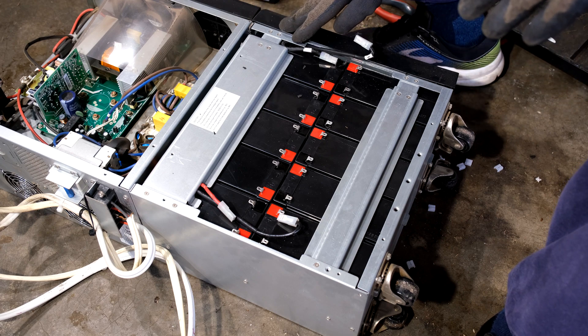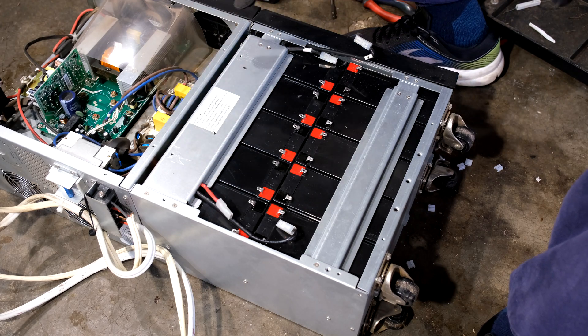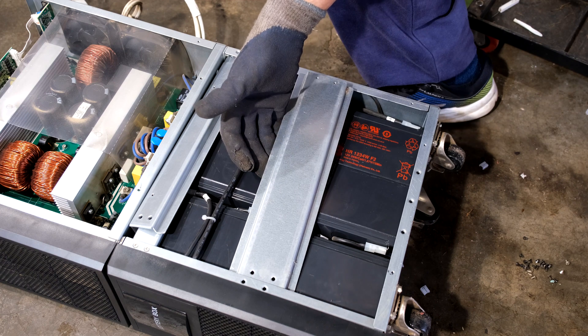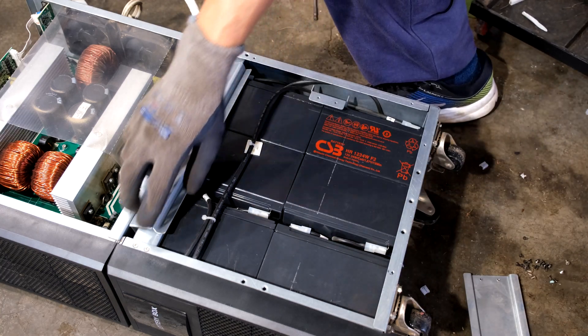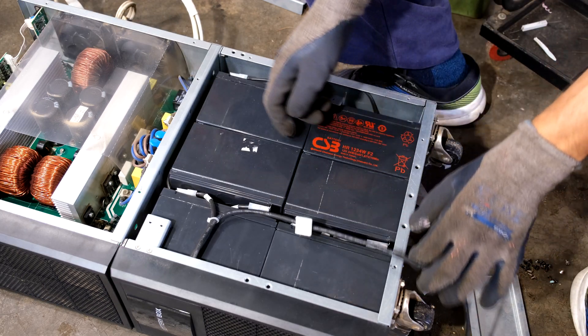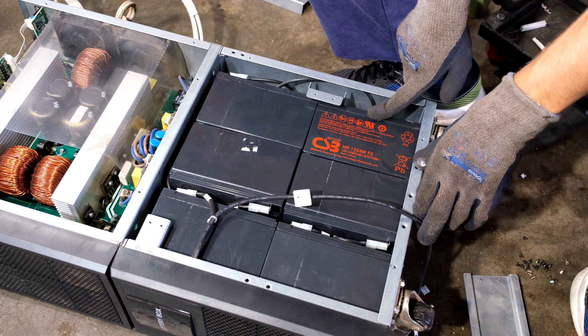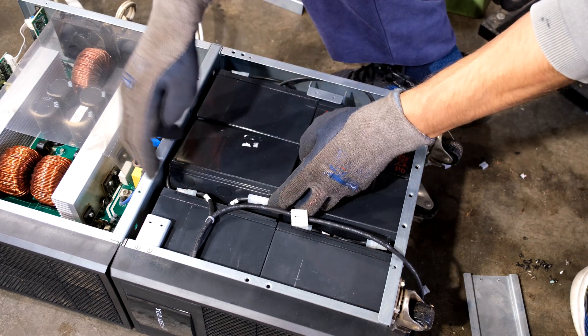I'll connect these once I've connected the other side — you can see I've left this open specifically. Now I'm going to flip it and do the other batteries. There was a plate over here which I had already removed — the camera didn't show it, sorry about that. Remove that plate and the fastening plate. I've removed this wire and you can see this battery is flipped the other way — that's very important.